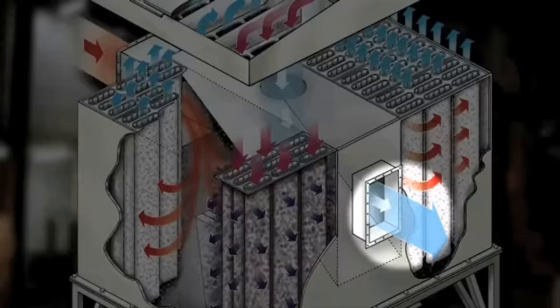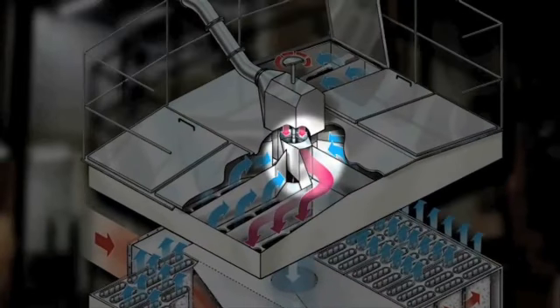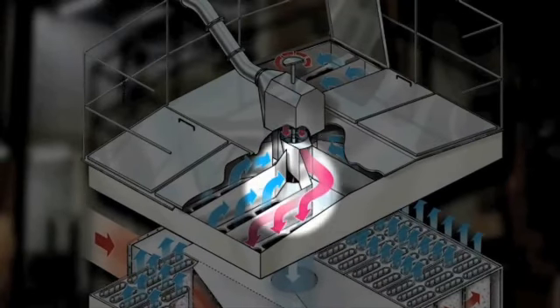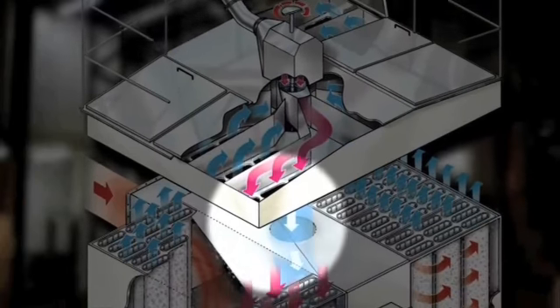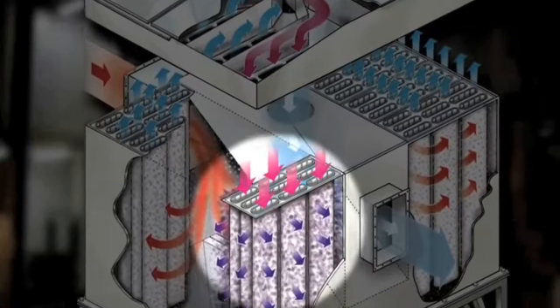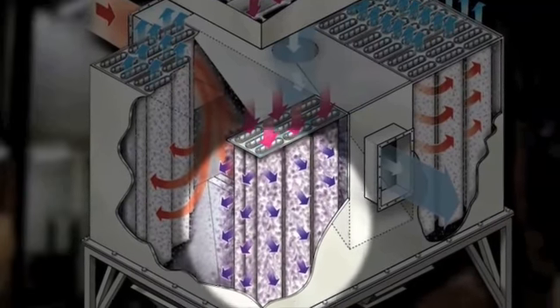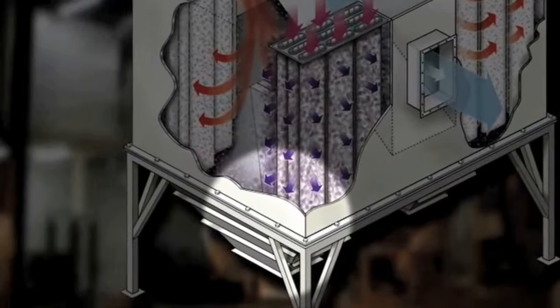The air is directed to the center shaft and then passes down to the clean side of the center section and out of the filter. The compartments in the filter top are consecutively isolated by the cleaning nozzle. This operation blows air in the opposite direction down through the hoses to clean out the filter bags. The dust falls down into the hoppers and is removed by a pneumatic transport system. This cleaning method also eliminates pressure peaks in the production line, helping to reduce disturbances in the process.